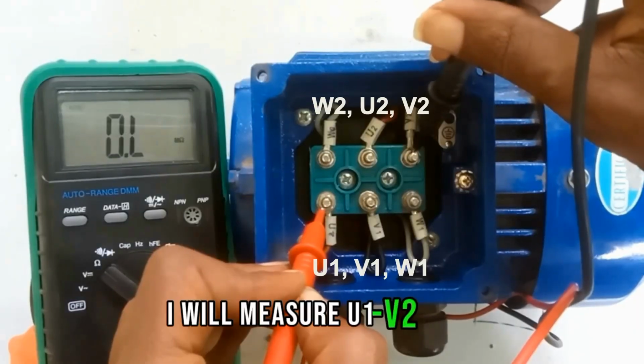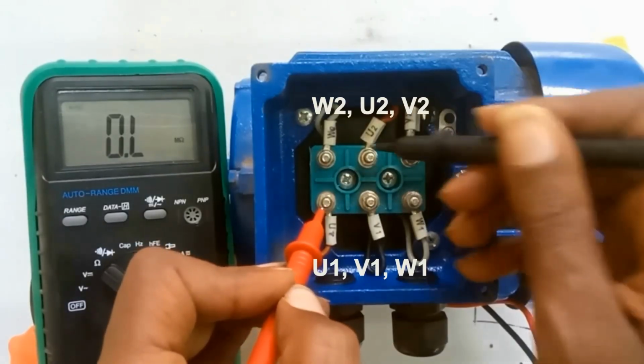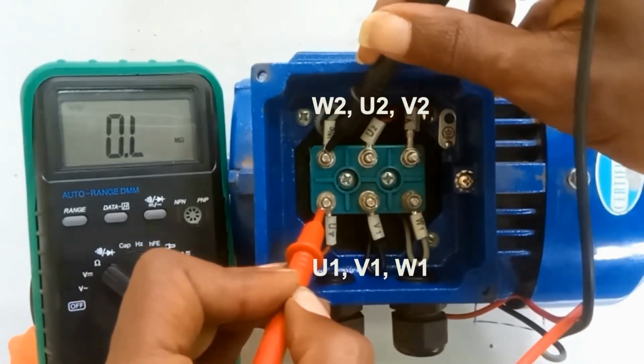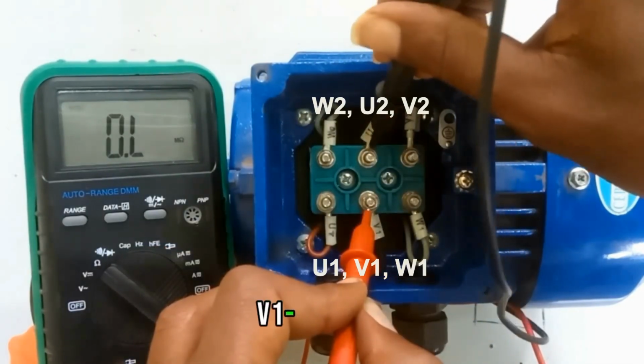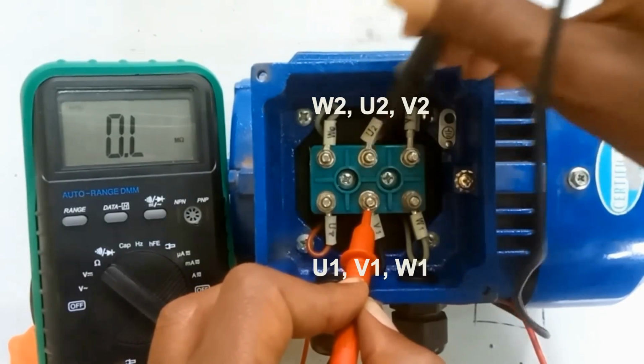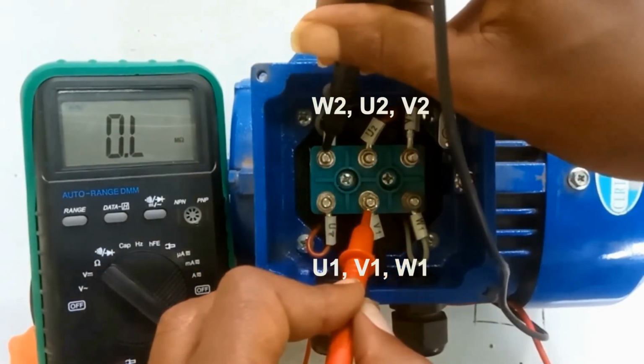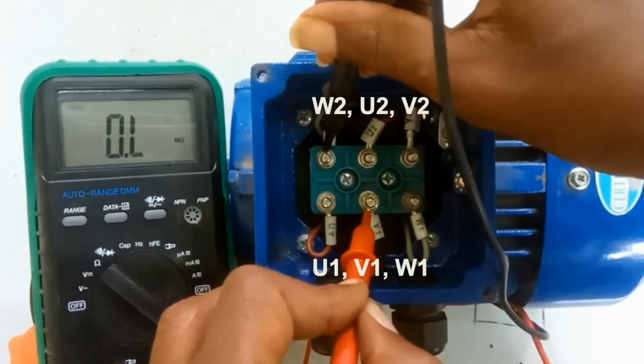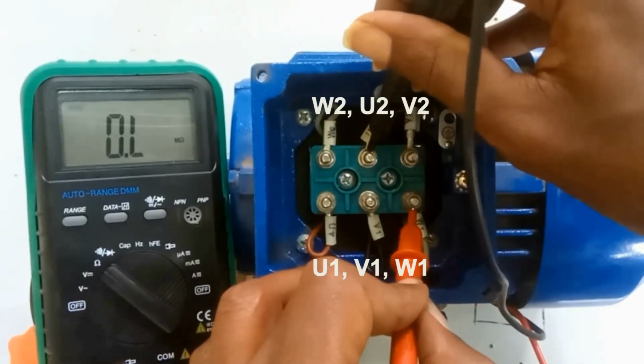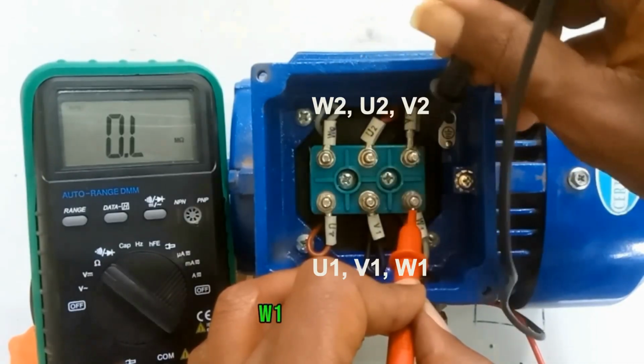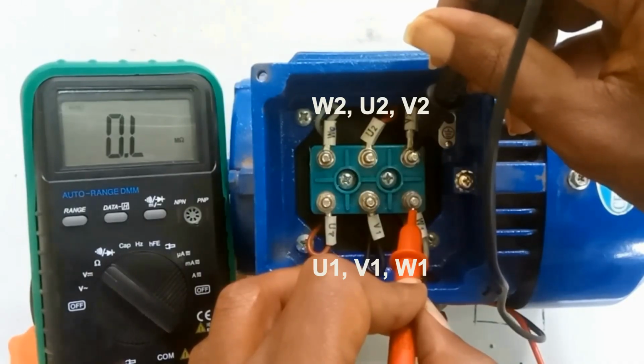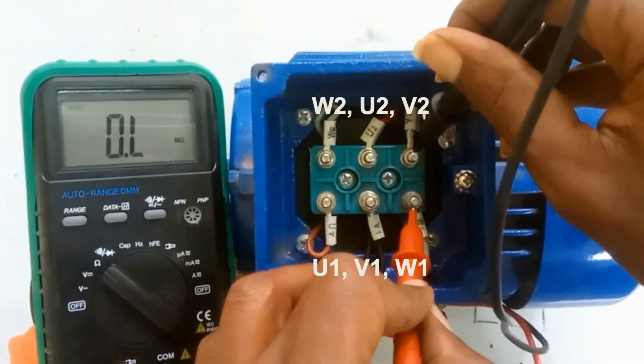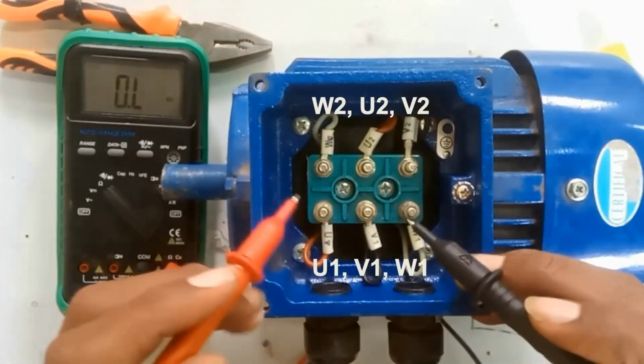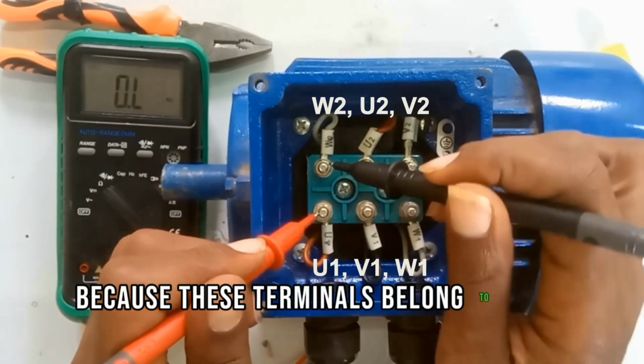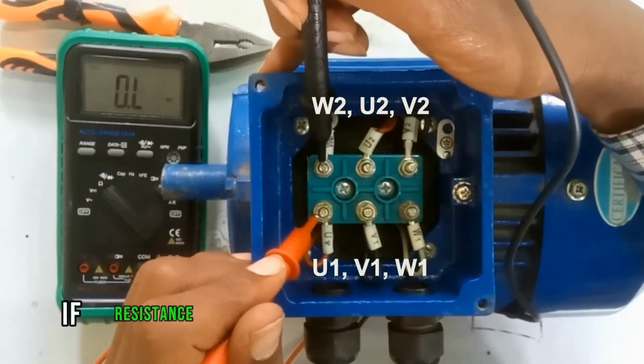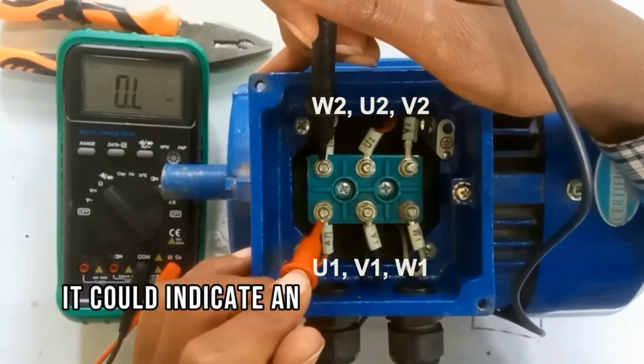I will measure U1 to V1, U1 to W2, V1 to U2, V1 to W2, W1 to U2, W1 to V2. As you can see, there is no resistance reading between these terminals. This is normal because these terminals belong to different windings and are not directly connected. If resistance appeared between these unrelated terminals, it could indicate an internal winding fault.